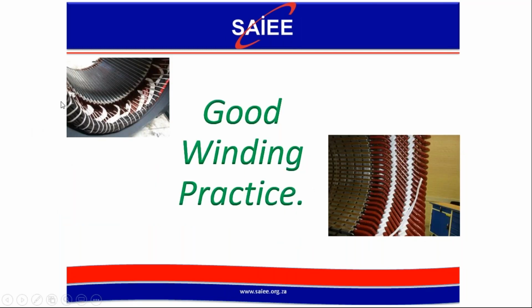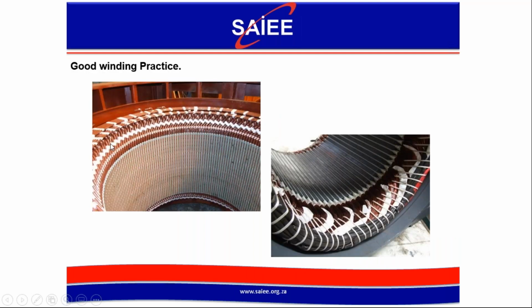Good winding practice: we look at what can be done to maintain efficiency on rewinding a machine, improving efficiency, and keeping the life of the machine to expected values. I have a number of photographs and calculations on what we consider good winding practice. Some photographs again on the machines show why it's important to have a certain amount of lashing on the machine and support on the coils to restrict the movement of the coils. Because any movement there could cause chafing and damage to the coil and premature failure of the machine itself.